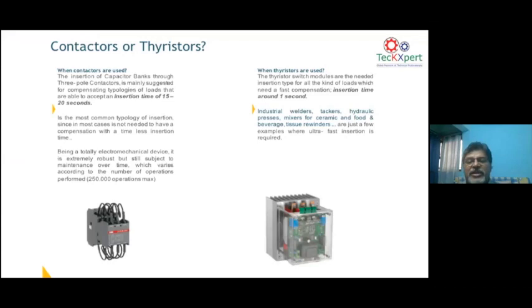Sometimes these oscillations you can control by using thyristors, because conventional contactors take a few seconds to switch on, as the contactor has its own time delay. But in a thyristor, your switching time is much faster. Take a 20 millisecond cycle: you cannot bring a contactor to switch on in 20 milliseconds. Even a thyristor cannot do it in 20 milliseconds, but at least about 60, 70 milliseconds, in 2 or 3 cycles, is the only delay that will happen with a thyristor. That means you are able to bring the power factor correction much faster than a contactor.